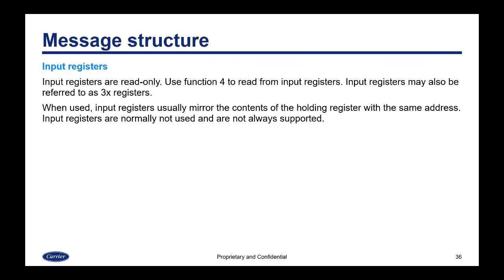Input registers are read-only. You use Function 4 to read from input registers. Input registers may also be referred to as 3x registers. When used, input registers usually mirror the contents of the holding register with the same address. Input registers are normally not used and are not always supported.